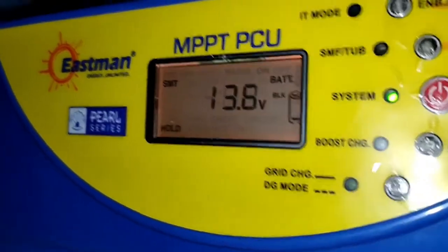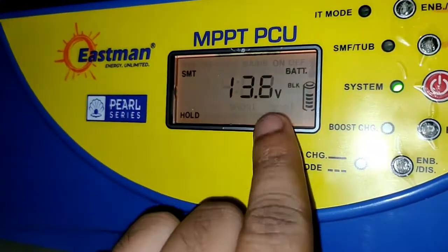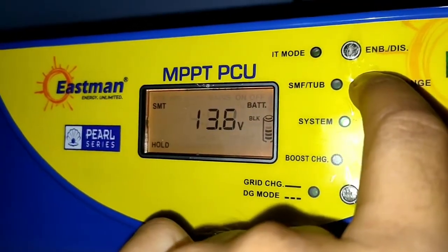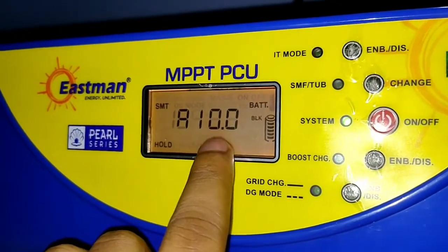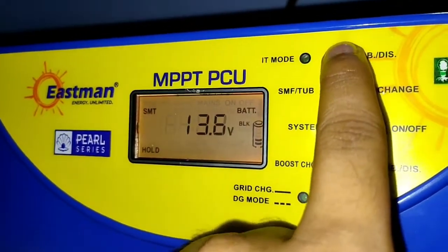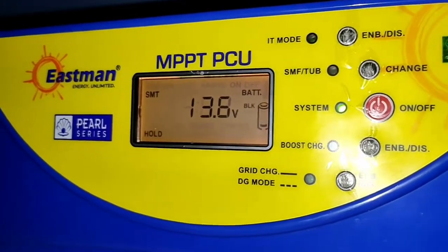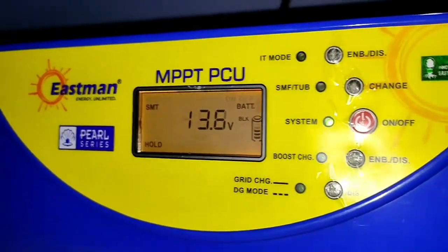The voltage has increased to 13.8 volts. Let's check what the current is given to this battery now — it's 10 amperes, maintaining that level. I will also show you in a graph how this charging stage looks.